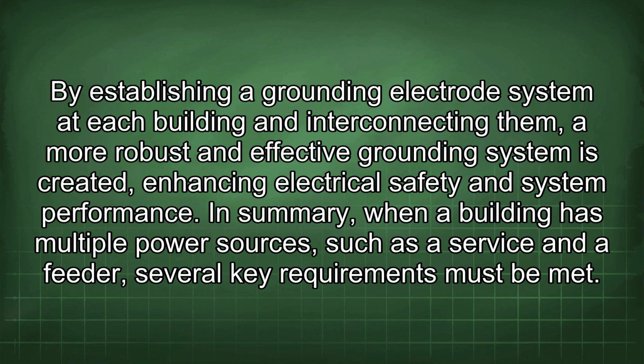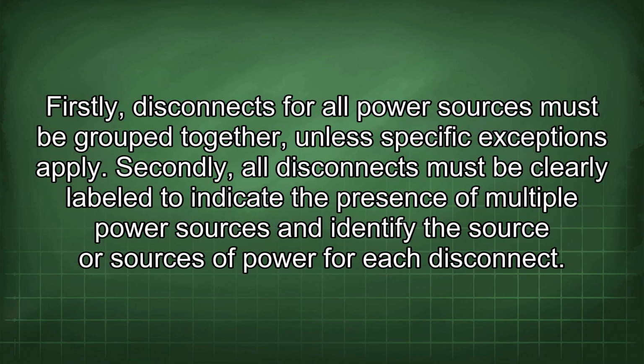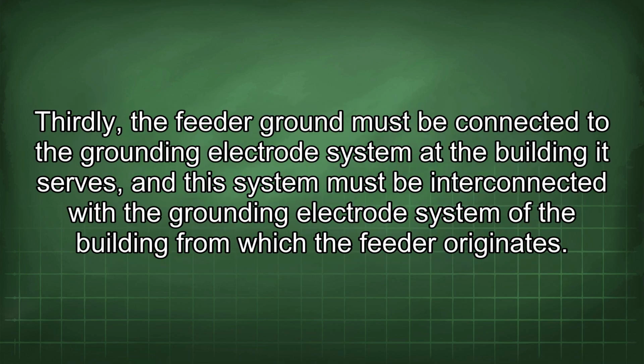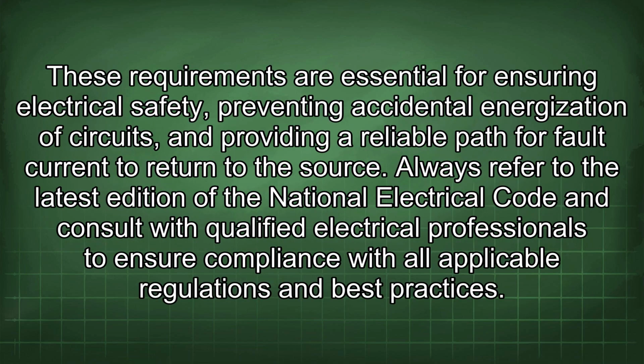In summary, when a building has multiple power sources, such as a service and a feeder, several key requirements must be met. Firstly, disconnects for all power sources must be grouped together unless specific exceptions apply. Secondly, all disconnects must be clearly labeled to indicate the presence of multiple power sources and identify the source or sources of power for each disconnect. Thirdly, a feeder ground must be connected to the grounding electrode system at the building it serves, and this system must be interconnected with the grounding electrode system of the building from which the feeder originates. These requirements are essential for ensuring electrical safety, preventing accidental energization of circuits, and providing a reliable path for fault current to return to the source. Always refer to the latest edition of the National Electrical Code and consult with qualified electrical professionals to ensure compliance with all applicable regulations and best practices.